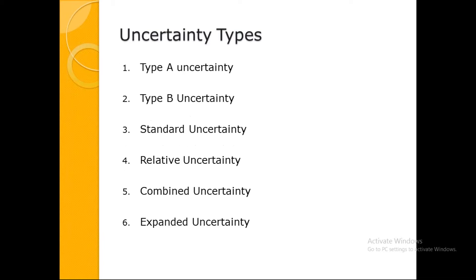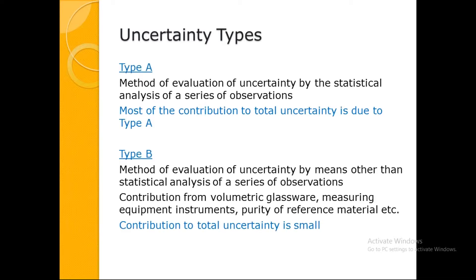There are Type A and Type B uncertainties, standard uncertainty, relative uncertainty, combined uncertainty, and expanded uncertainty. Type A is the method of evaluation by statistical analysis of a series of observations — like the chloride analysis where we took multiple readings. Whatever uncertainty we obtain from performing multiple readings will be called Type A uncertainty. Most of the contribution to total uncertainty actually comes from Type A.